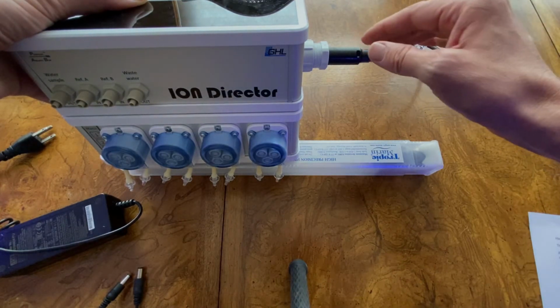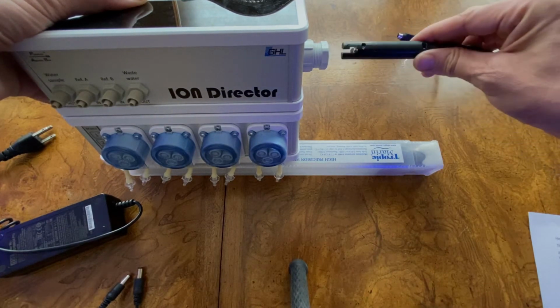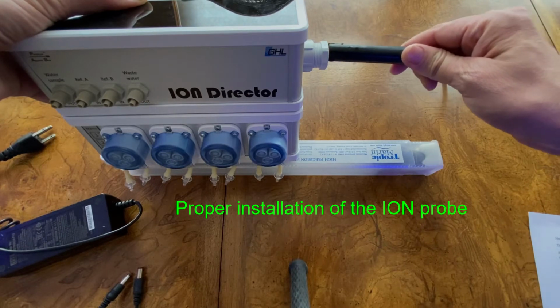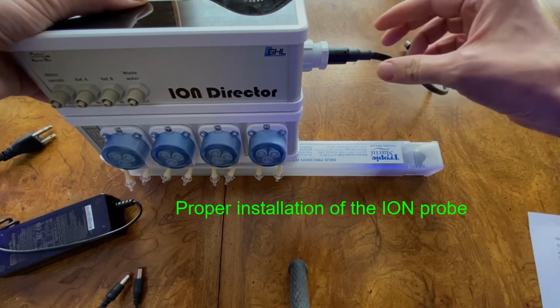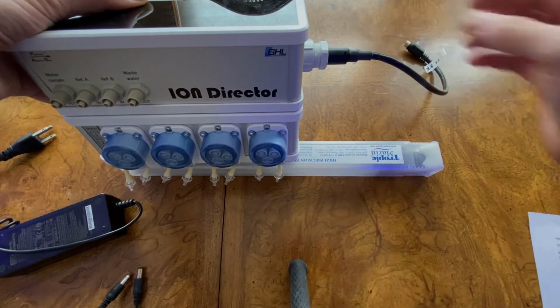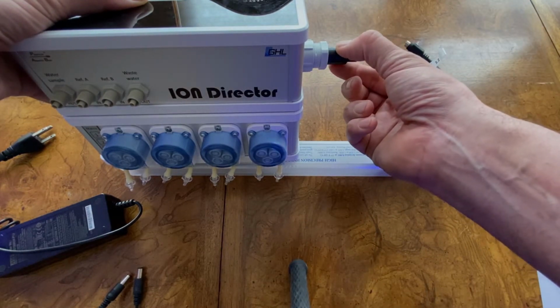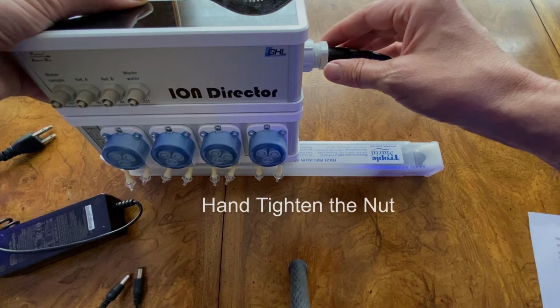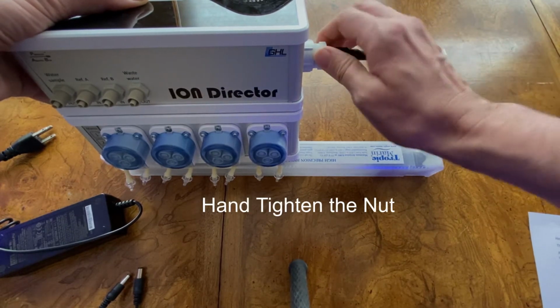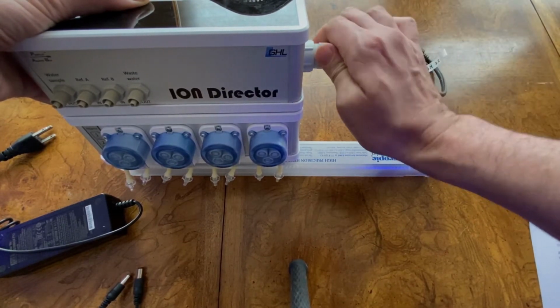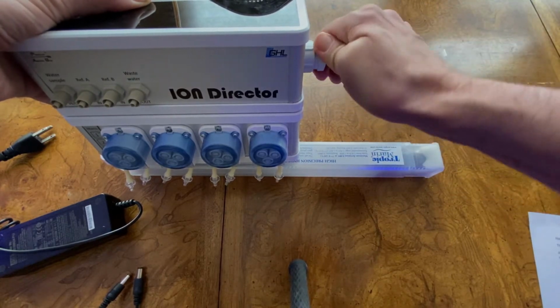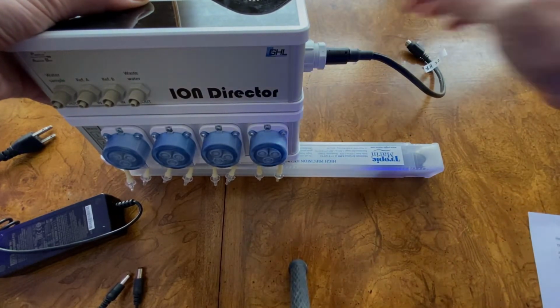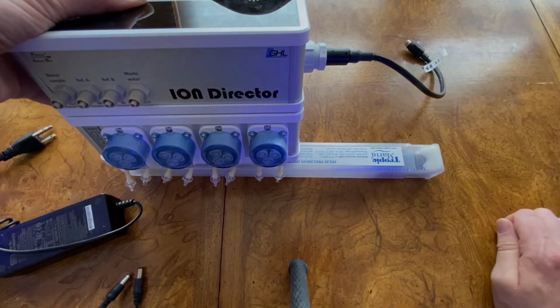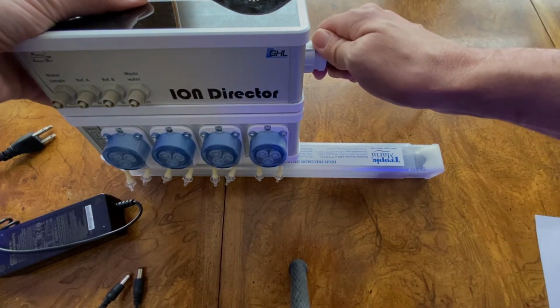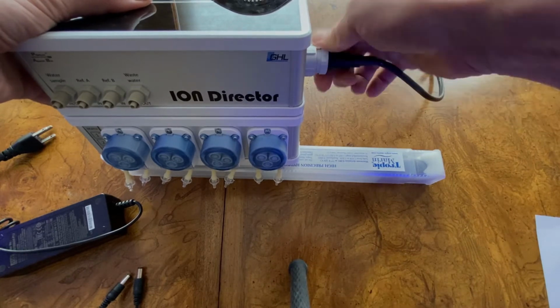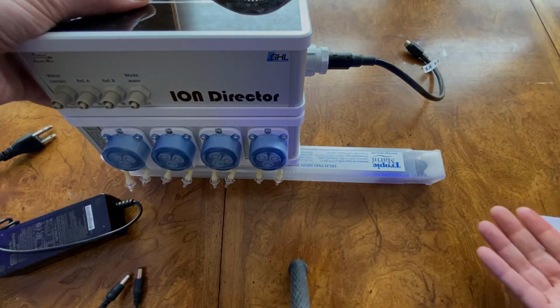I'm going to pull the probe back out, and I'm going to put it in properly, and then I'm going to slide it in. You're going to notice now that it's actually in more, that it's slid in all the way. Once you have slid it in all the way, you're going to want to hand tighten the nut. And again, what I have learned while using and testing the unit is that hand tightening the nut is all that's required for proper installation. A really good tight fit. You don't need to take a wrench to this. And again, we'll monitor it during the initial setup to make sure that there are no leaks there.